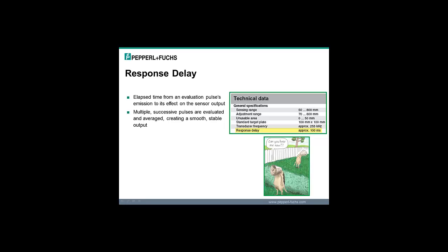A little earlier in the presentation, we discussed response time of ultrasonic sensors and that they were a little bit slower than a photo eye or a little bit slower than inductives. If you look in the technical data sheet, you'll see a response delay specified for an ultrasonic, and this 800 millimeter range model you can see is about 100 milliseconds. Now that 100 milliseconds, what that tells you is the elapsed time from the sensor's pulse being emitted and the effect of its information that it gets returned on the output. So there's a little bit of a delay.